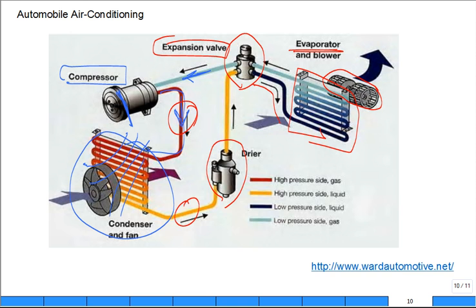This is a very interesting device — I'm passing it around. It has two inlets and two outlets. It basically senses the temperature of the refrigerant leaving the evaporator. There's a bulb in the middle that senses the temperature of the flow going through it. It's filled with gas that expands when warm and contracts when cold. It's connected to a diaphragm which accentuates that expansion and contraction, controlling a little needle valve. When it expands because it's warm, it lifts the needle — more refrigerant flows. When it's too cold, it collapses, pushes the needle down, seats it, and shuts off the flow. It's a thermostatic expansion valve — a control mechanism.